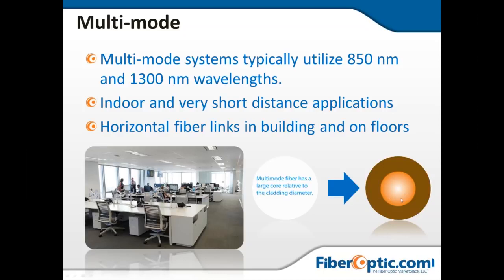You'll never have multimode that travels that far because, from the industry specifications, it's really meant to be at a maximum of like 2 kilometers, and even at that, it's really expecting like 10 megabits per second transmission rate. So you're looking at maybe fire suppression systems, signaling systems, for signs or something like that. Very, very low bandwidth applications that you'd be looking at.